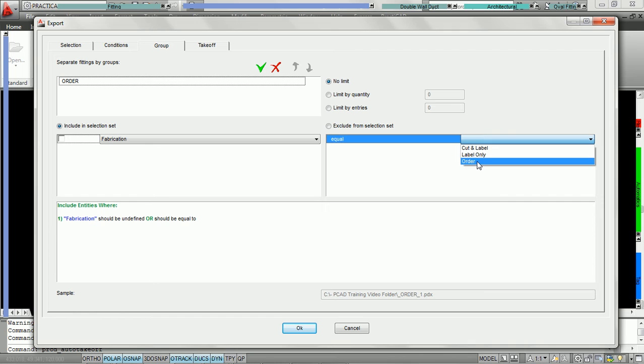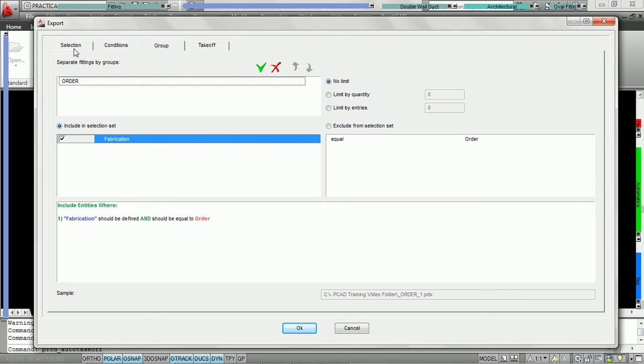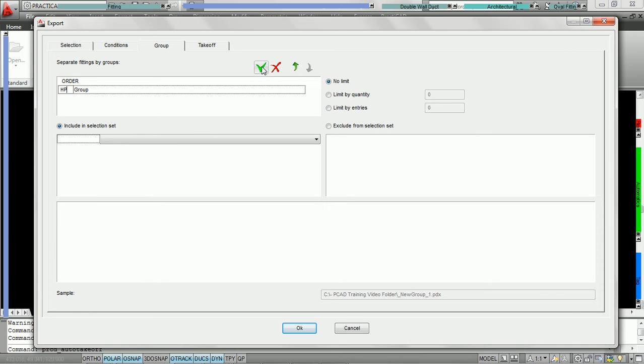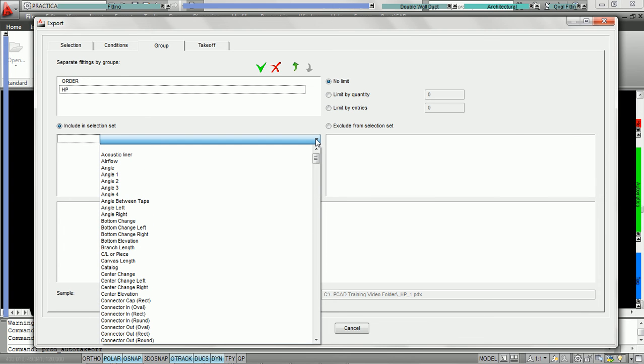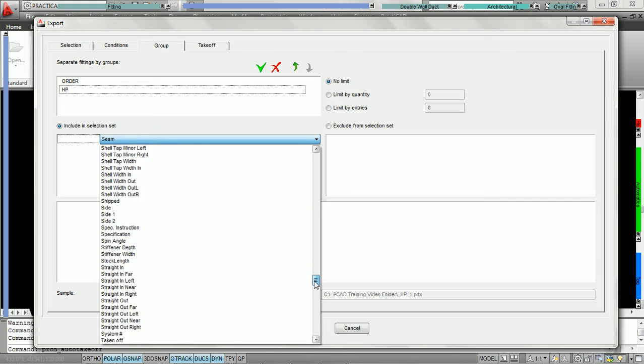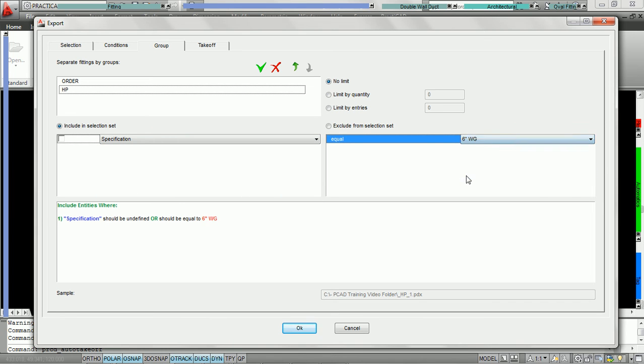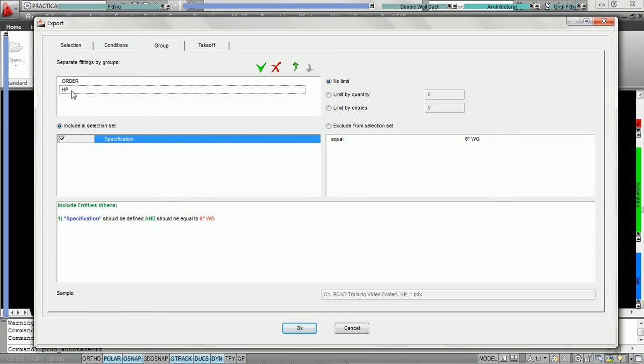Here you can see the three fabrication levels. By doing this, we'll have a group created called 'order' if some of the duct in our selection criteria has the fabrication level equaling order. Next, we're going to hit add again and add a second group — we'll call it HP for high pressure. We'll set the condition: if specification equals 6 inch water gauge, we want it to go to the high pressure group.